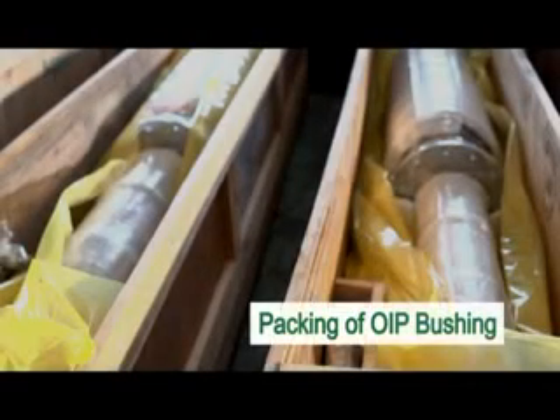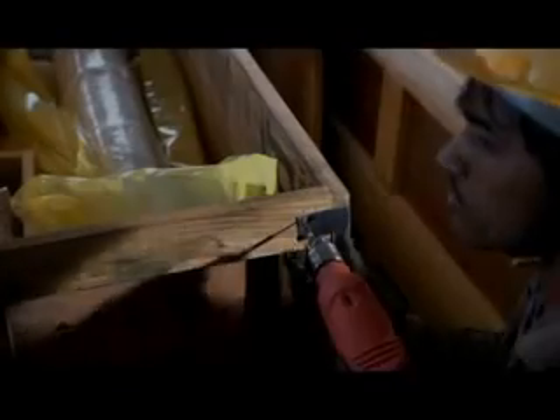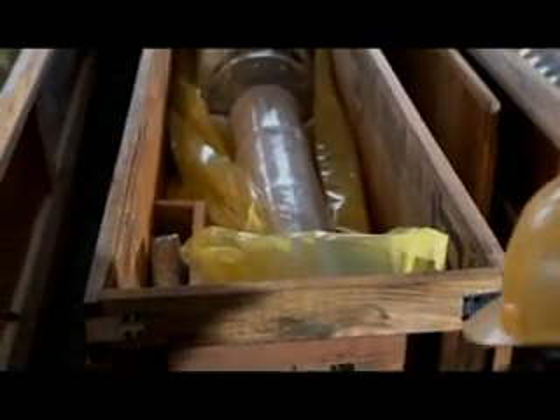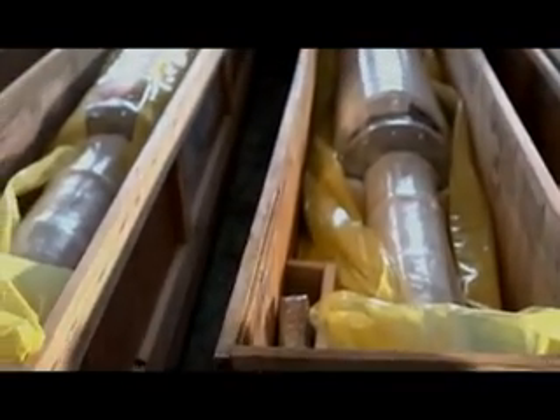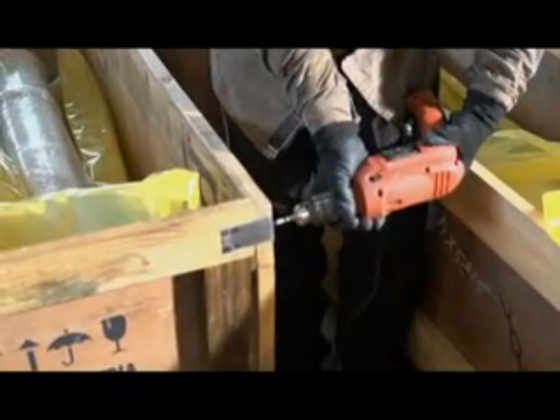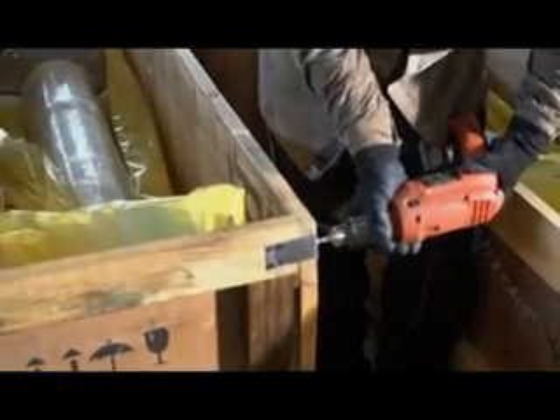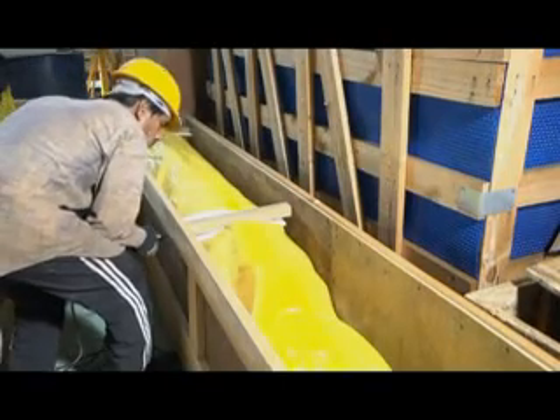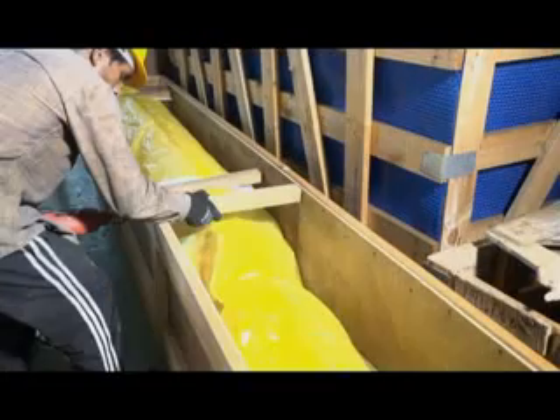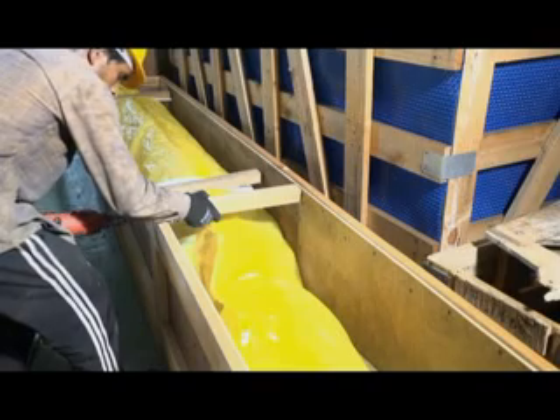Packaging and storage of OIP bushing. To prevent physical damage to the bushings, generally only one bushing is packed in one wooden case. The bushing is placed in the packing case at an angle of 6 to 8 degrees to horizontal. Accessories like arcing horns, terminals, etc. are also packed in the same packing case.